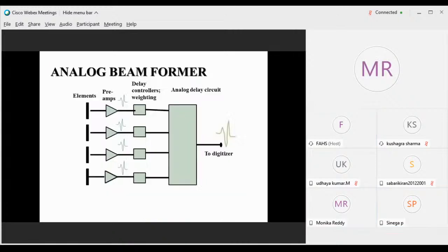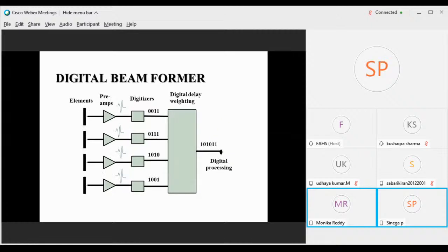So the analog beamformer is the same, but it will pre-amplify the signal and give it to the delay controls. Then it will give it to the analog delay circuit, where the image processing will be done in an analog format and given to the digitizer to process the signal. And in the digital beamformer, what will happen? Instead of analog, we are using digitizers which will convert the signals into binary format, and they'll code that and then give it to the digital delay timers, and then digital processing will happen.